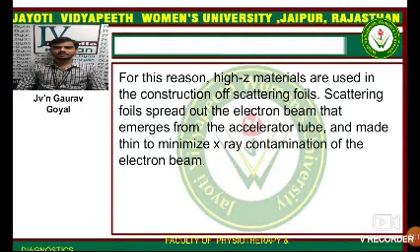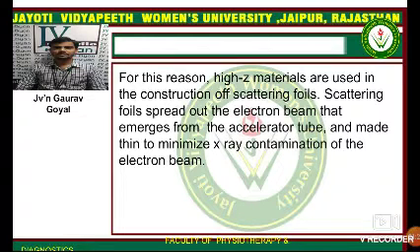For this reason, high-Z materials are used in the construction of scattering foils. Scattering foils spread out the electron beam that emerges from the accelerating tube and are made thin to minimize x-ray contamination of the electron beam.